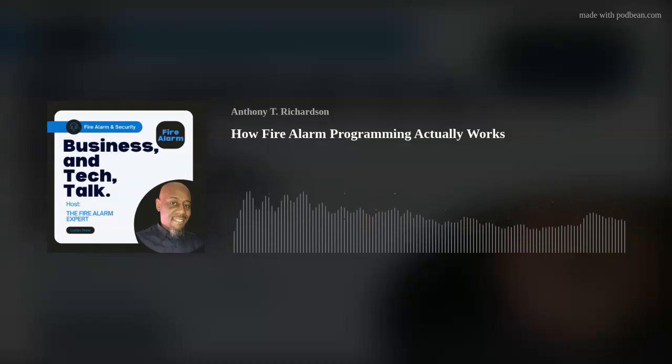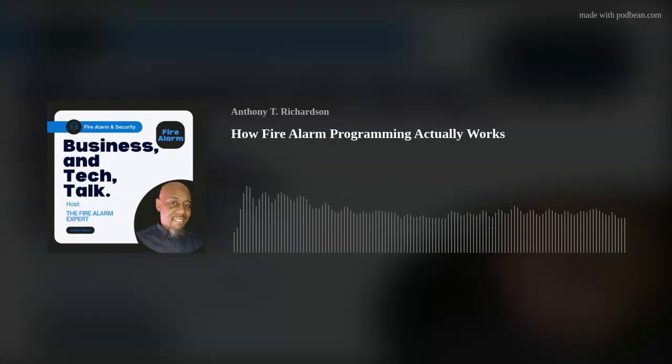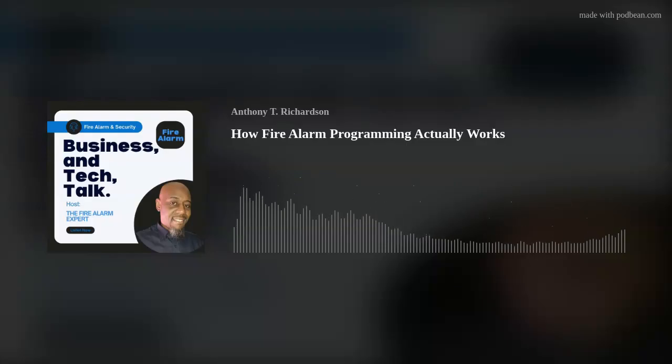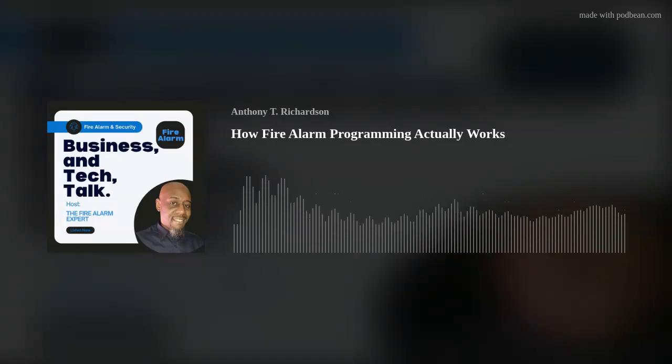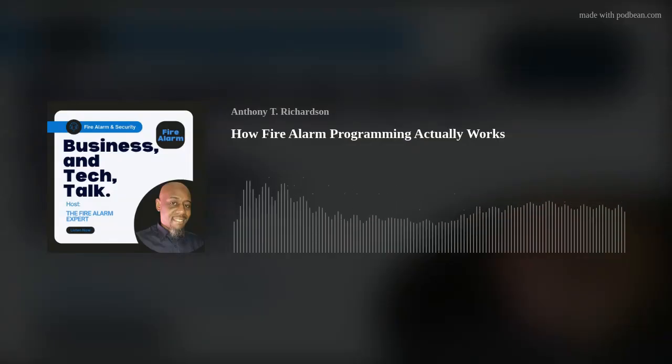The easy way for us to do it when it comes to a Kidde system or an Edwards system, the quickest way, if you have voice, I don't know of any system that you can upload voice to, but what you would have to do is unplug some things and start copying some labels, taking pictures or videos, whatever you have to do, so that you can get those messages correctly, and especially test the system so you can actually see the functions, so that you know what you need to turn on in the case of an emergency.